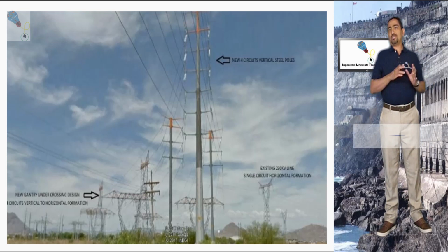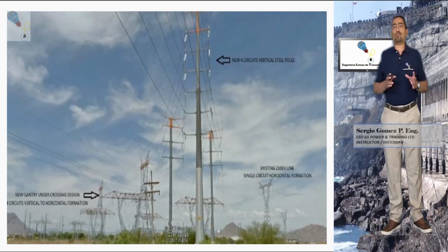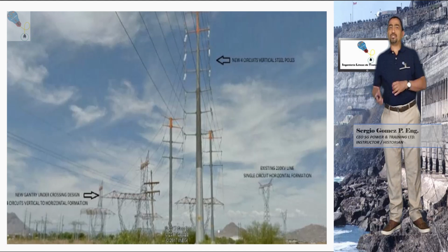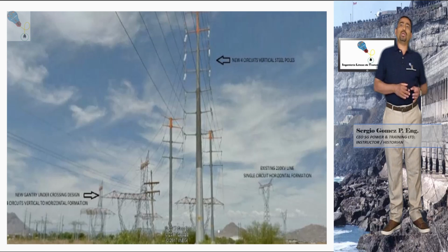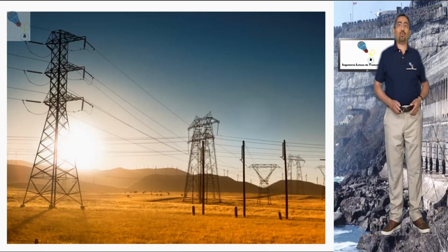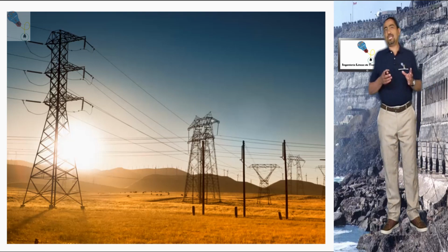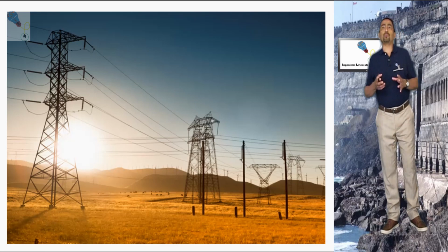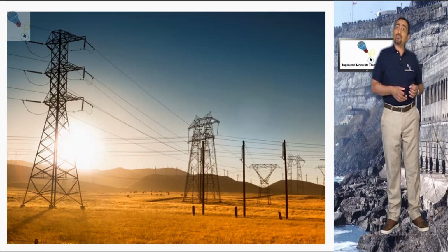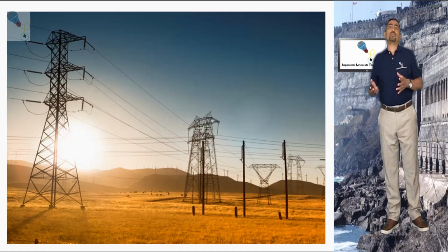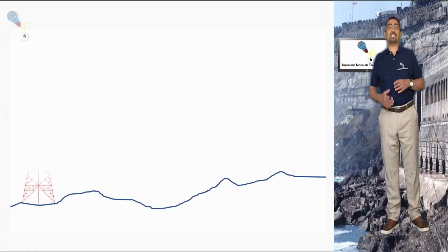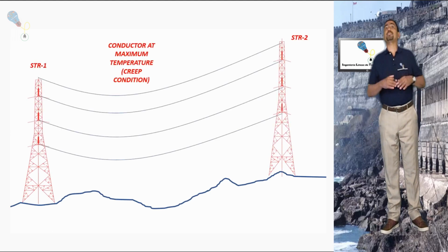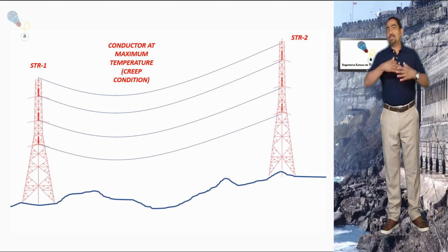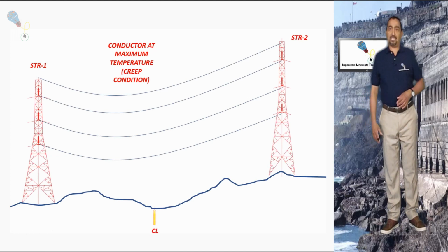Now we will talk about other types of crossings which do not necessarily require permits, but rather explanatory drawings. I refer to crossings between our new transmission line with other existing distribution or transmission lines. Basically, the crossings of high voltage transmission lines with a distribution line do not really require any type of documentation or permit. It is only required to meet the vertical clearances from the lower cable of the transmission line at maximum temperature condition and creep towards the distribution line of sight.